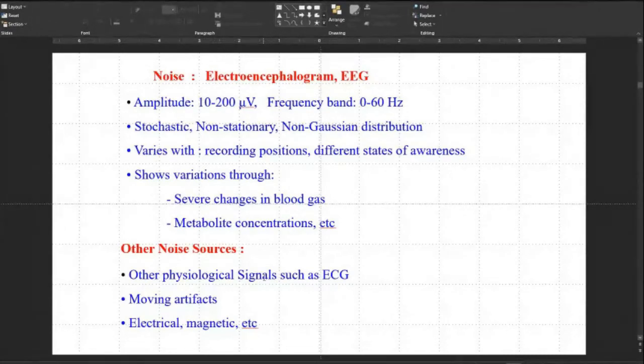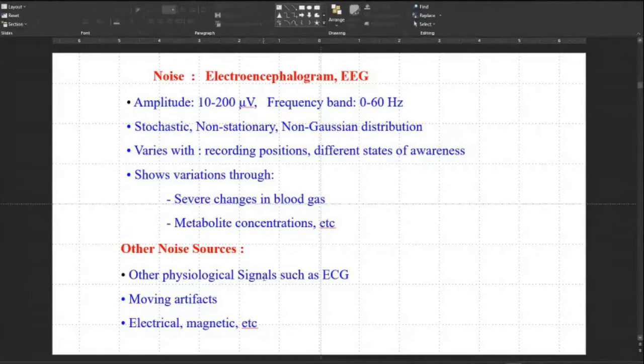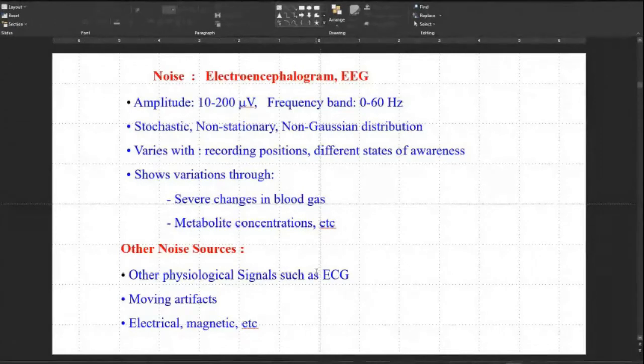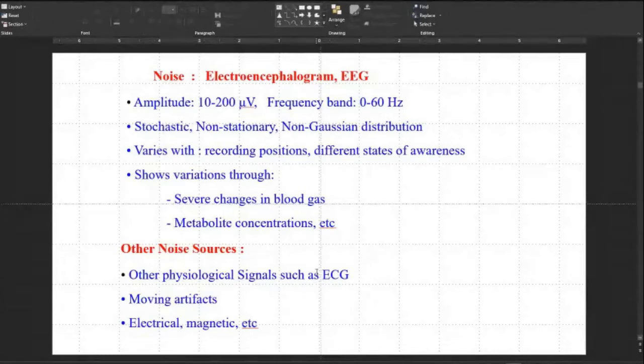There are also movement artifacts, especially important when recording infants or subjects with attentional deficits. A normal healthy person can only keep attention toward a problem for about 7–8 minutes. Electrical and magnetic noise from instruments — computer monitors, CPUs, fans, induction motors on the same power line — are all additional noise sources. There is a single signal source but thousands of noise sources.